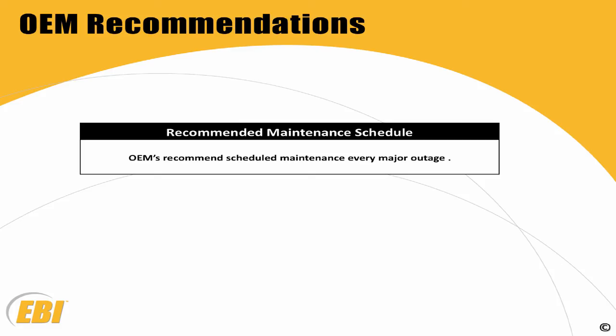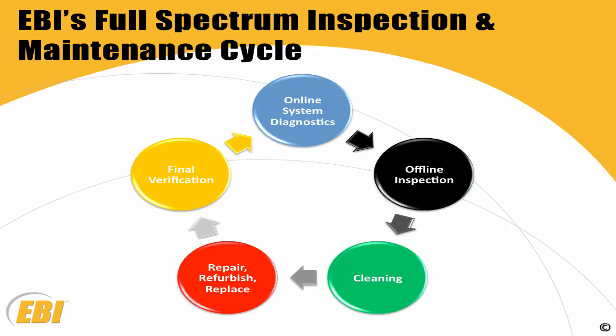The OEMs will recommend that you have a regularly scheduled maintenance program at every major outage. What EBI recommends is that this maintenance program goes full circle. You start off with an online system diagnostic like an EMI test. An EMI test will tell you the problems that you're having in your system. It will identify them, and it can actually pinpoint the areas where you're having your problems.